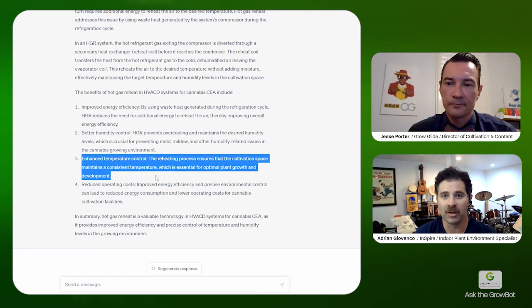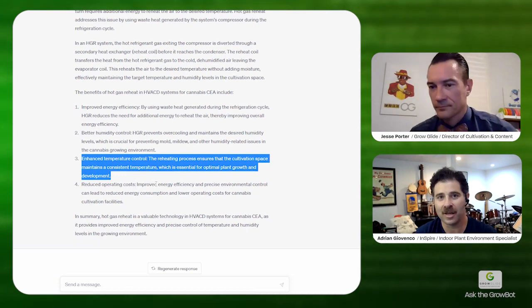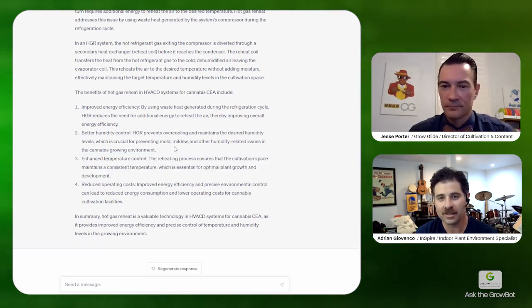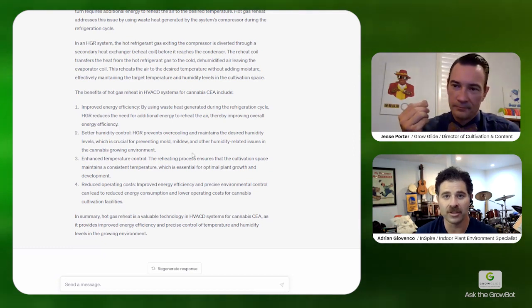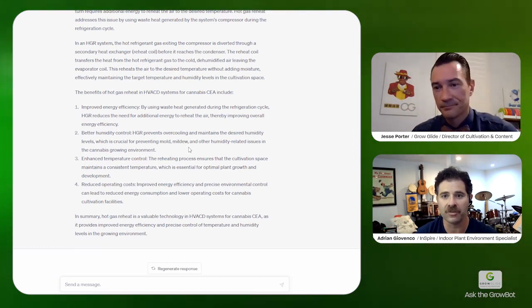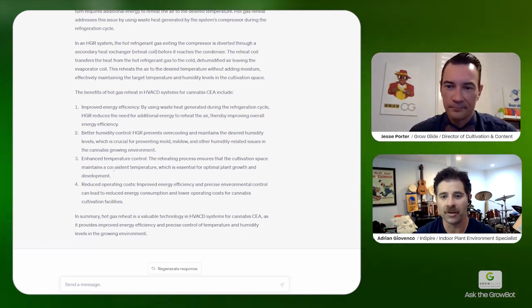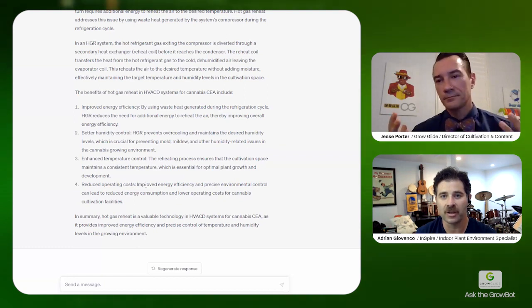You're always going to need some level of additional reheat, otherwise your rooms are going to be in the 60s. If you lose the hot gas reheat circuit, you've now lost another 10 to 15 degrees of reheat, which means that you either needed to upsize your ancillary heat system, which is what we generally advocate for, but it costs money. It's not free, right? And so this is all risk and reward and how you'd plan it all out, or you're just okay with losing about 10 degrees during that nighttime cycle typically.